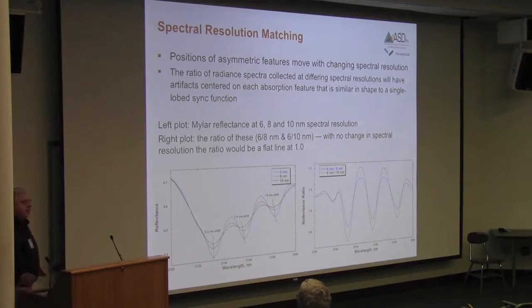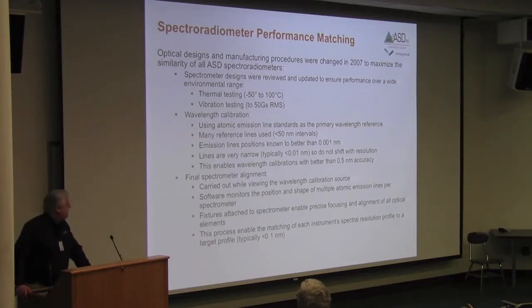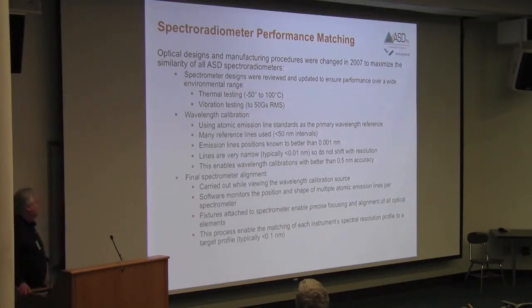This is part of the difficulty of what people use for wavelength calibration. Because if you use a reflective material like rare earths or things like that, the wavelength of those features is dependent on resolution. So it's not a single value. So one of the things that ASD wrestled with, I guess about 8 years ago now, was that if you want to do a lot of things with a spectrometer, like quantitative analysis, and you want to be able to take a calibration that's done on one spectrometer and move it to another one, they really need to be relatively matched to one another. The resolution as a function of wavelength needs to be very similar from one unit to the next.